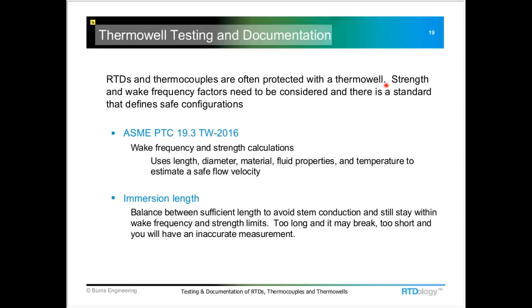Well, we'll take a look at that too in just a little bit. Thermowells do have probably the most testing and documents available of any of the components we've talked about so far. There's a lot that goes into it, and one of the most important ones first is the wake frequency and strength calculation. So I'm going to spend some time talking about that and how we balance the immersion length of the probe, which is the main governing factor in the strength, against the required immersion length to get a good accurate temperature measurement.